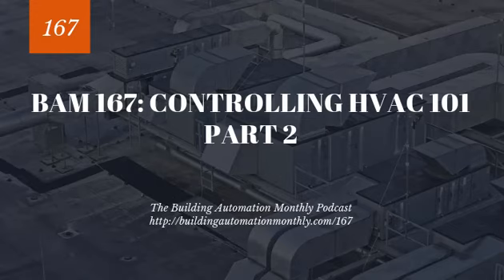So let's say you're in a temperate climate and you've got the air sitting there at 74, 50, so 74 degrees, 50% relative humidity. You're in that thermal sweet spot for ASHRAE 55. And you want to keep circulating that air, because why recondition all this air from outside when you can just circulate the air? So mixed air units are used for that.